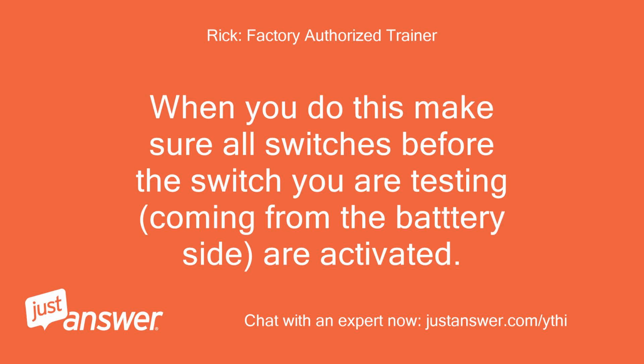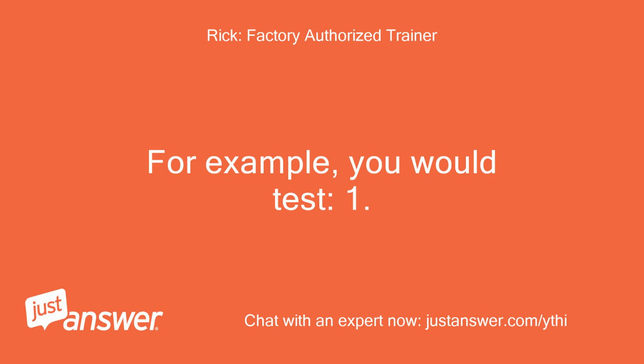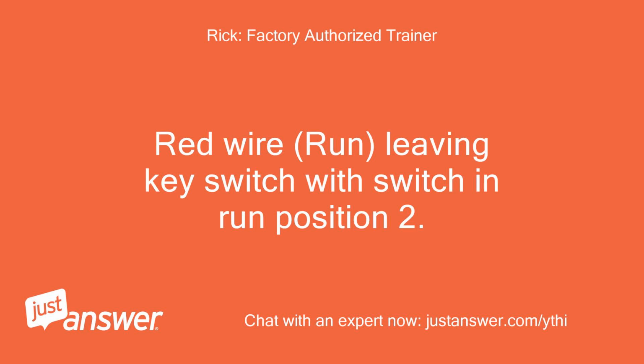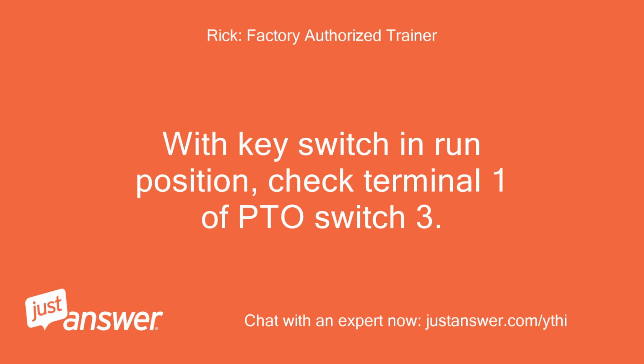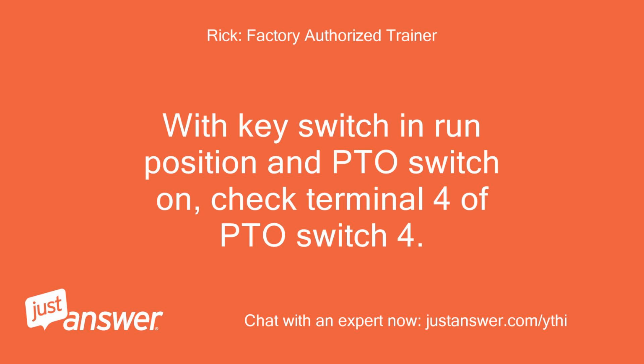When you do this, make sure all switches before the switch you are testing, coming from the battery side, are activated. For example, you would test: 1. Red wire, Run, leaving key switch with switch in run position. 2. With key switch in run position, check terminal 1 of PTO switch. 3. With key switch in run position and PTO switch on, check terminal 4 of PTO switch.